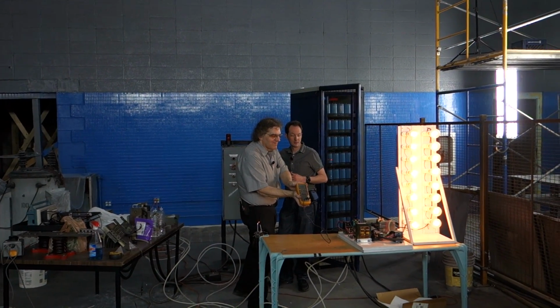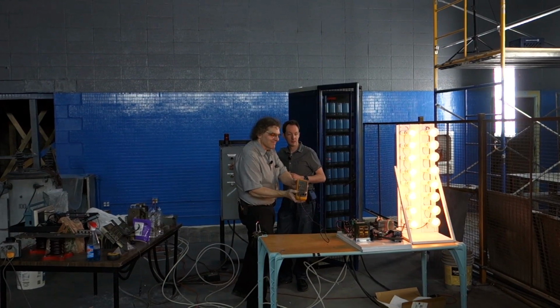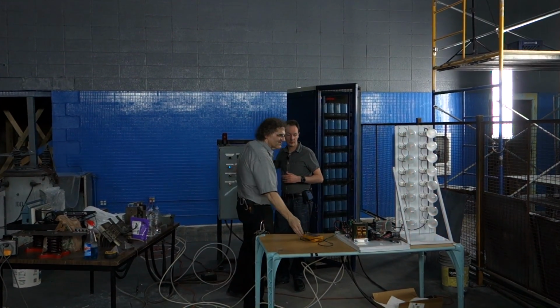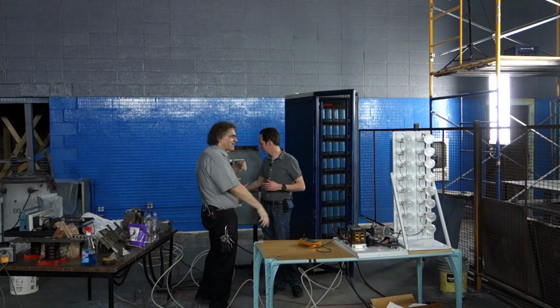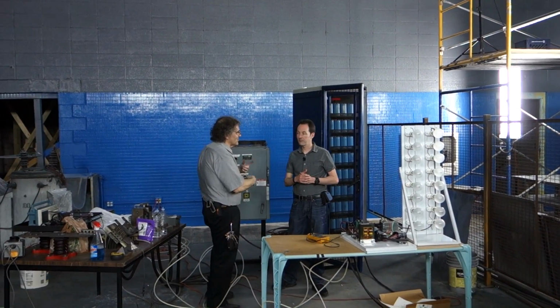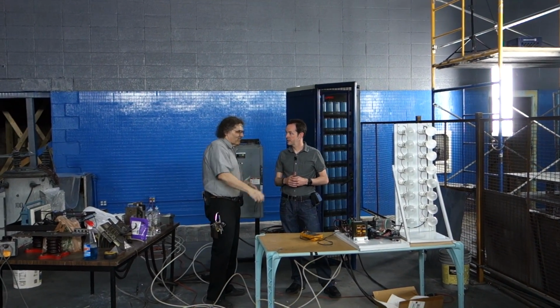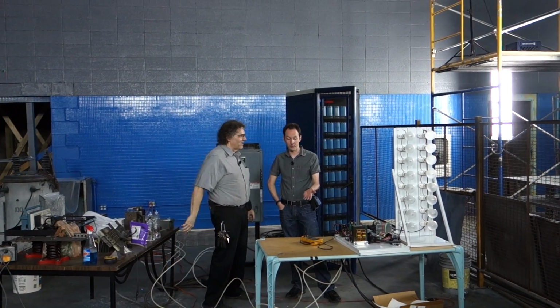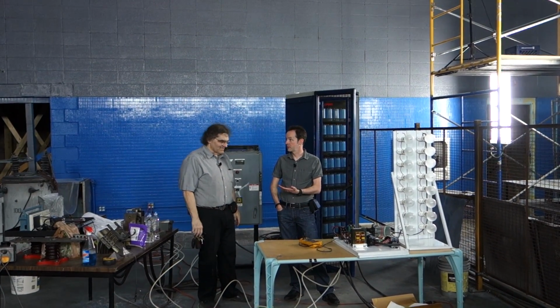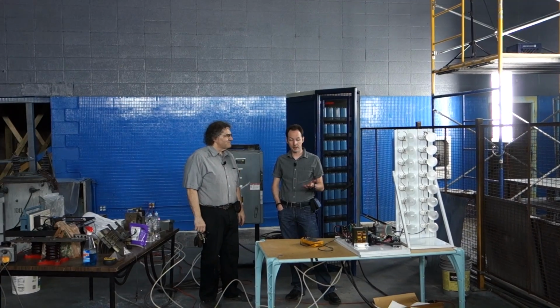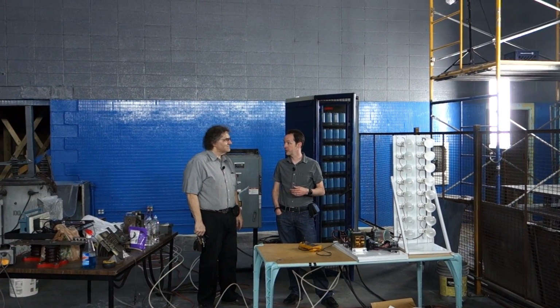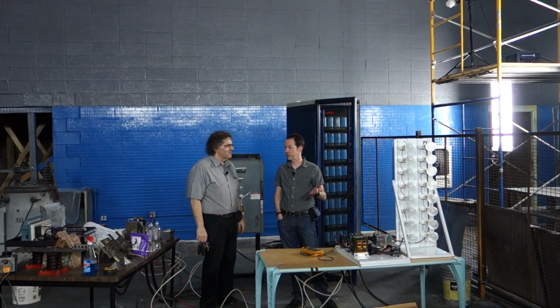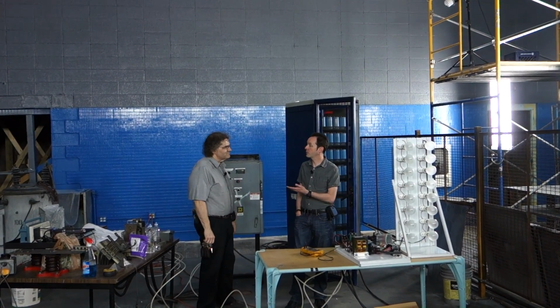So here's your design - I was thinking maybe we could cut out some, because you want 4 amps, but if 20 amps is our limit, that's what we got. Well, that's what the circuit breakers are here for. Exactly, and we might have to have a slightly beefier circuit breaker, because if we're drawing a straight 20 amps for like a minute and a half, what were we drawing before?